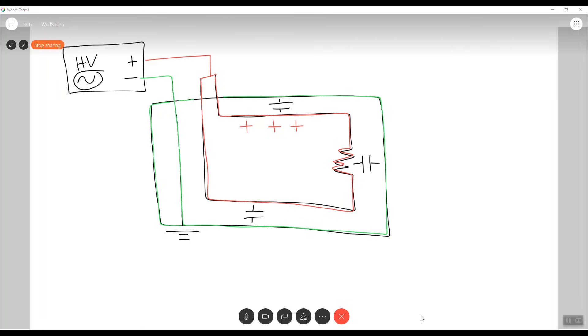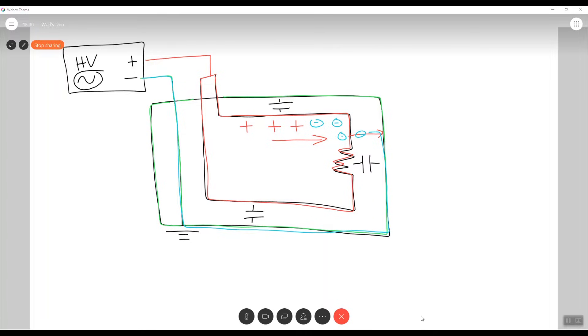What we want to know is: will any of the electrons floating on our line and neutral, which have now been given this force and energy to want to break through this insulation — will that happen? If electrons do find their way through, they will be returned to our instrument and measured by how much leakage has occurred. If there's a complete breakdown, that means those electrons have found a path through almost as a short, and our Hypot tester will report a breakdown.